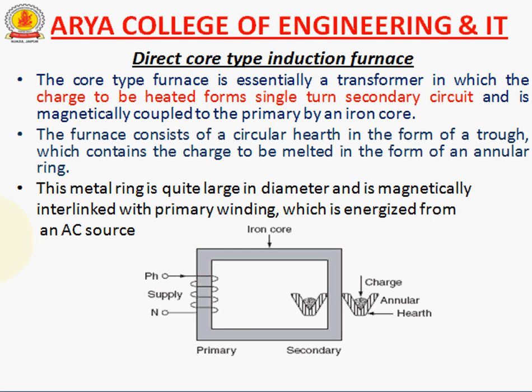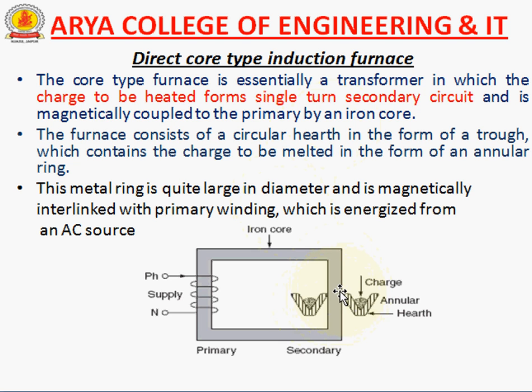Now we are going to types of induction heating. First of all, direct core type induction heating. In this heating, there are two windings: primary winding and secondary winding, connected such as like a transformer. The core type furnace is essentially a transformer in which the charge to be heated forms a single-turn secondary circuit, magnetically coupled to the primary by an iron core.